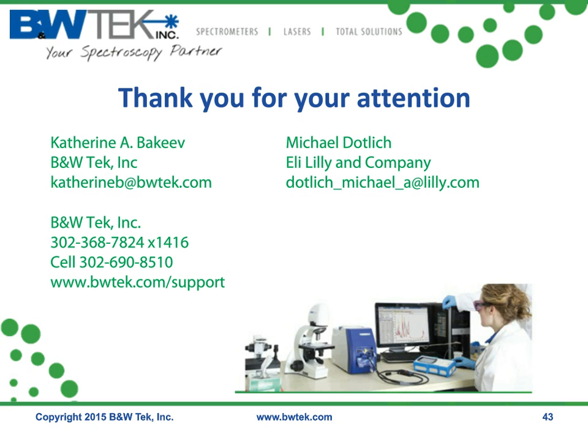Catherine, does the portable iRaman Plus have different excitation wavelengths other than 785 nanometers? Yeah, the iRaman Plus is available also in 532 and 1064 wavelength excitation. So for samples that are highly fluorescing, 1064, the longer wavelength, is more appropriate. But yeah, the iRaman Plus does come in three different wavelength excitations.